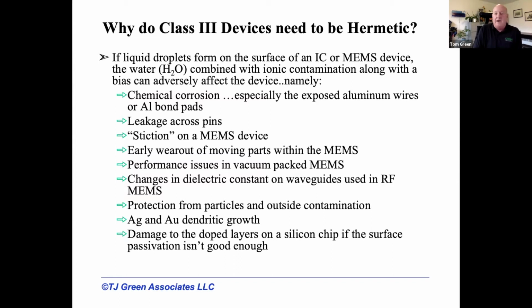But if you had a leaker and you just had the molding protecting the inside of the component, well, then it's not that long before moisture saturates that header. It's in, along the interface between the molding and the feed-throughs, and voila, if you had a leaker to start, it's going to fill up with moisture. And you can ask the question, why do these medical devices even need to be hermetic? Well, if you look back through the literature, one of the biggest issues facing microelectronics is keeping them free of moisture. There's just a ton of papers and problems that have occurred over the years that are really moisture-related failures.